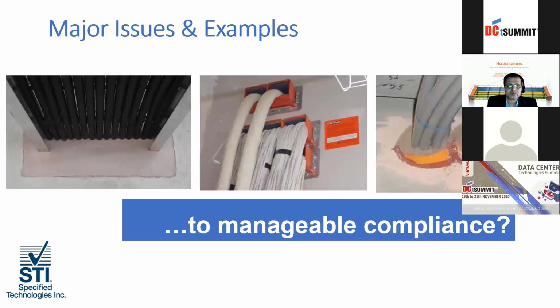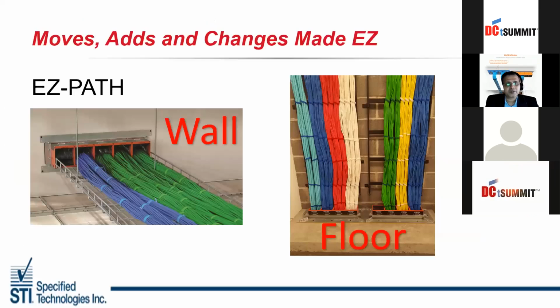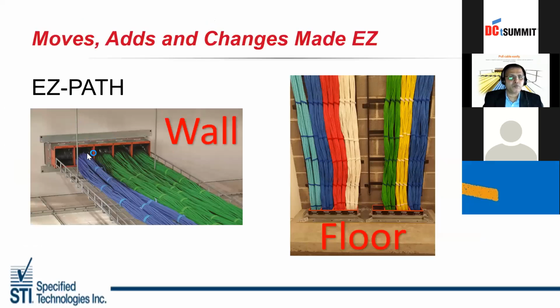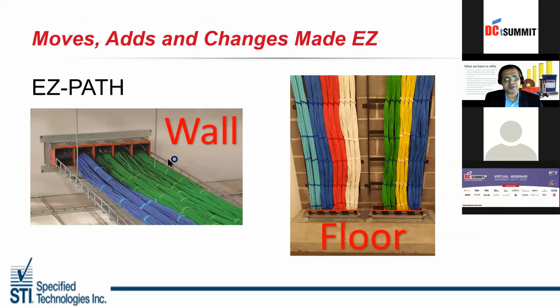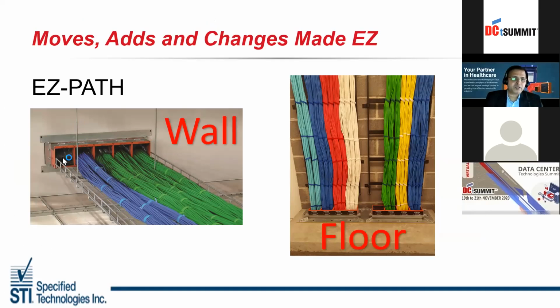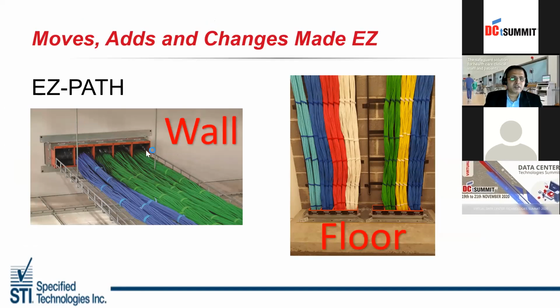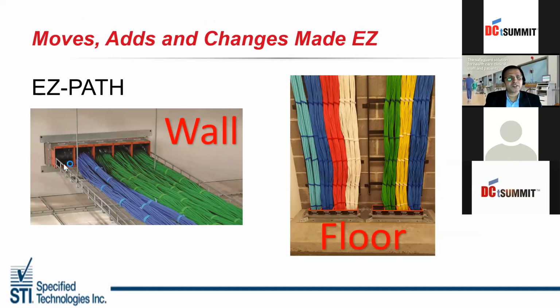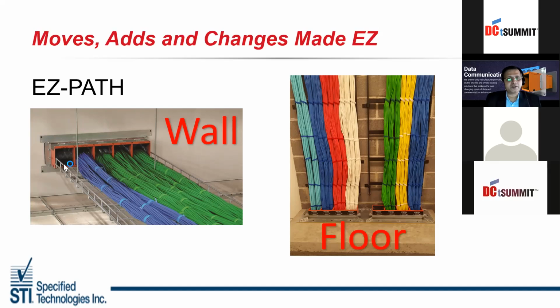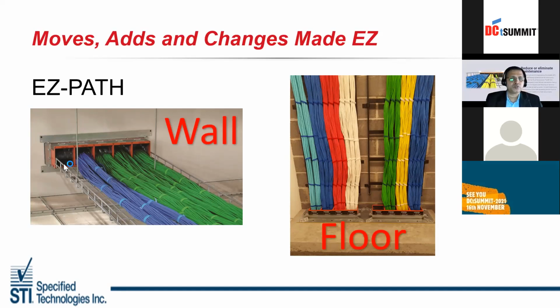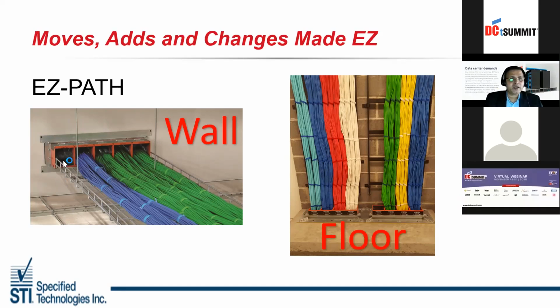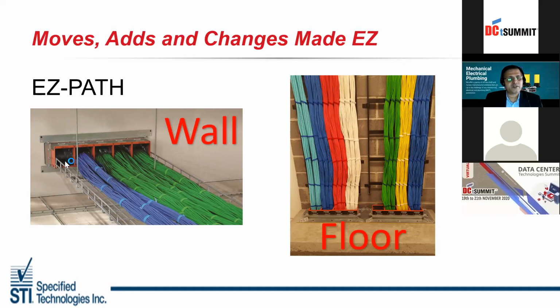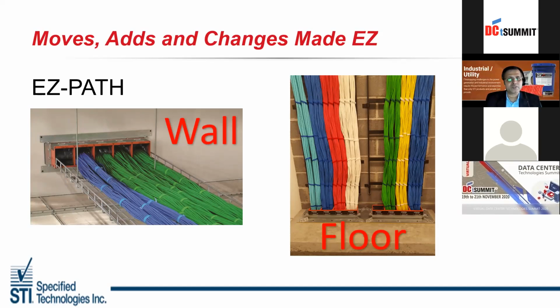EZ-Path, as I mentioned, can be for wall, it can be for floor. It can be easily ganged. You can see the cable tray passing through the wall, and these cables can be easily ganged. Now, if you see here, there are 1, 2, 3, 4, 5. The cables have been segregated. The last one is kept for future cable entries. After, say, 1, 2, 3 years, cables have to be added. So this is an additional provision. Even if it is zero cable, this will act as a fire stopping device in such scenarios.